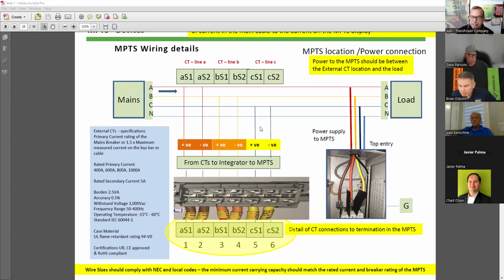I think I understand what you're saying there. So you've had instances where somebody mixes up the positive or negative, or flips the CT in the reverse direction, and they thought they could just flip the two wires to reverse the CT. Correct. When in fact CTs are designed with a specific polarity due to how they wrap the coil around the conductor. Correct. So emphasis on understanding what CT you have and where to install it into the equipment is crucial to avoid those very painful shutdowns or repeat shutdowns that frustrate a lot of people involved.